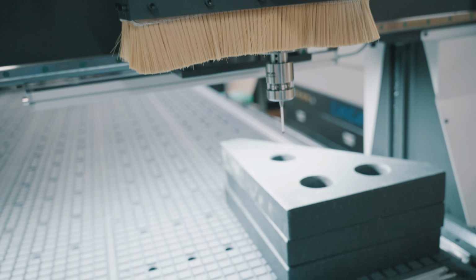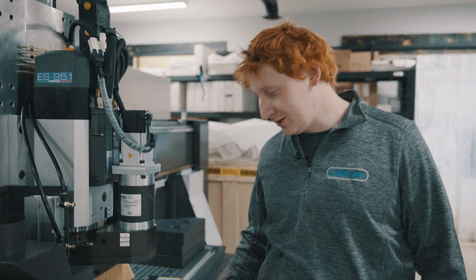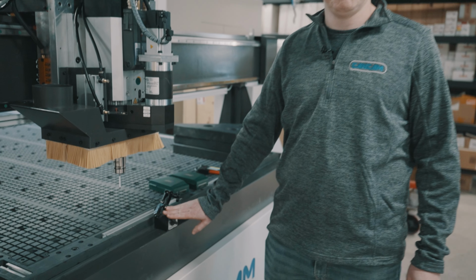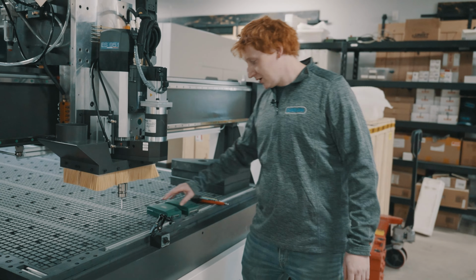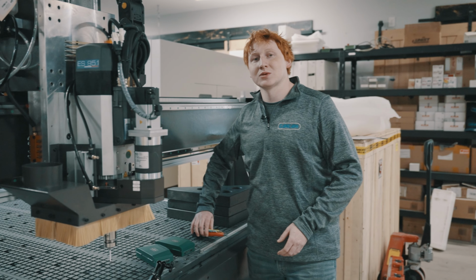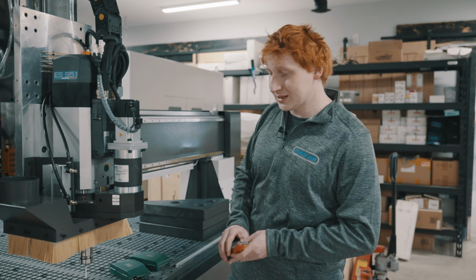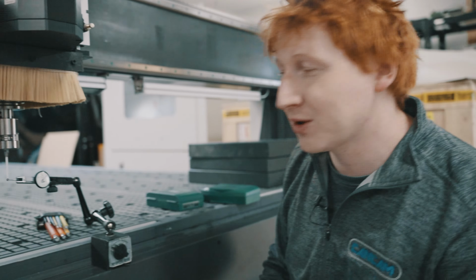To do a calibration on our probe, we're going to need a few things. First is our magnetic base, a 1/1000th indicator, as well as a 10/1000th indicator for further refinement. Last thing is we're going to need an Allen key set, preferably in metric. To do a calibration on it, we're going to set up our indicator so it just touches off on our probe, the base. You can do refinements with this screw, and we want to just touch the tip off and get it close to 0 here.